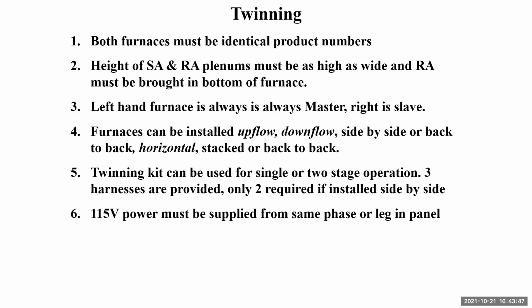Twinning. This is kind of a going history right now. When we're talking our twins, we're talking identical twins, not fraternal. They have to look identical. BTU ratings, boards, everything has to be identical. If you do get a board, don't quote me on these numbers, but we'll use a 34 board and a 61 board. Say the old one's a 34 and it's superseded to a 61 board now. Replace that board in both units. If one goes bad, they're both bad. Replace them both, unless you can get identical boards, or you will end up with problems. Again, we're identical twins. We're not fraternal. Everything has to match. And there are no triplets in furnaces.